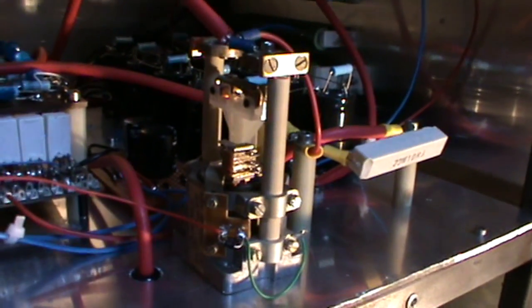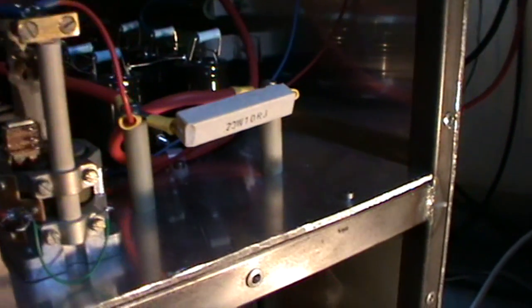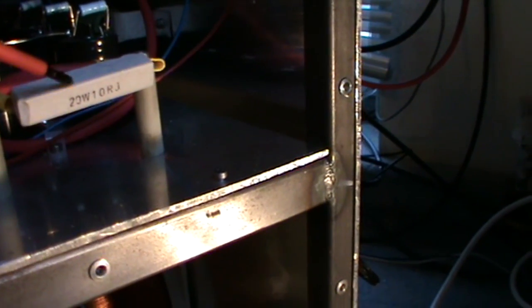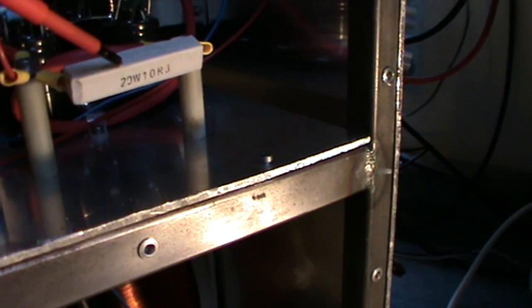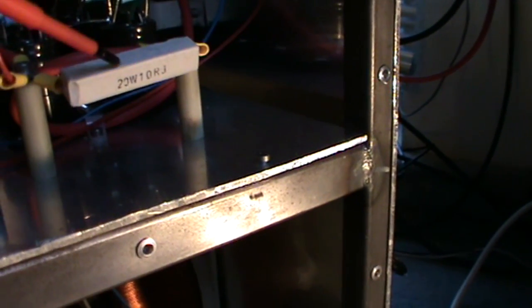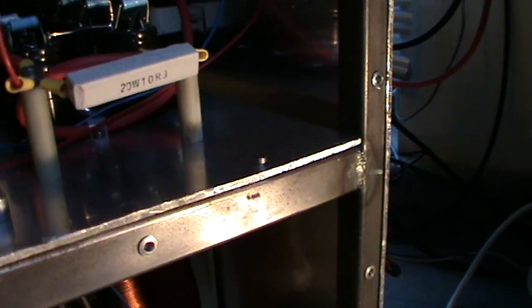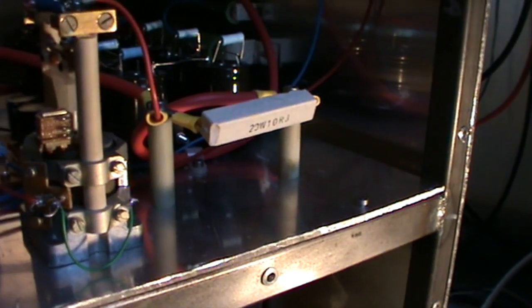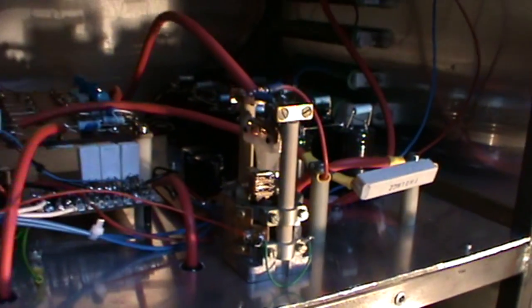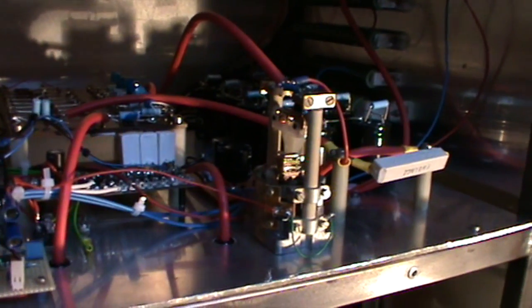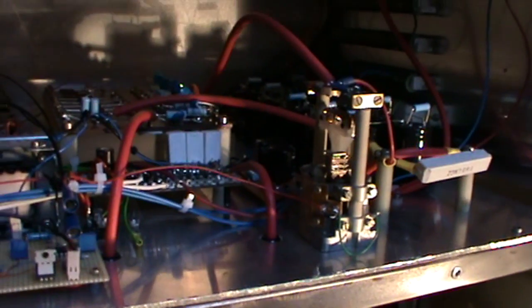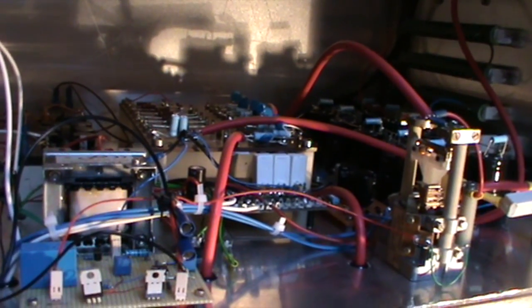If you're building these sort of high voltage supplies, you've got to have a number of safety features in there, it's usually good practice. That here is a 10 ohm wire wound resistor, which we call the glitch resistor, in series with the HT. So if there's a sudden current surge, that will also blow if, for instance, this doesn't. It's a number of safety factors you have to take into consideration when dealing with such high voltages. It's designed to be quite an industrial power supply, and if you pay attention to these details and make it relatively safe, it should provide good years of service.